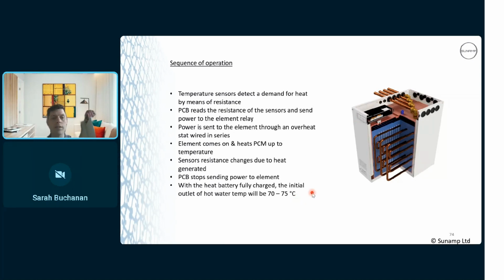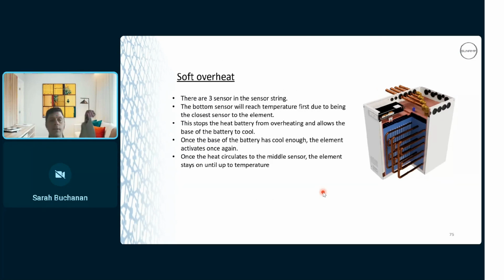With the heat battery fully charged, the initial outlet of the hot water will be 70 to 75 degrees, hence your TMV requirement. Your soft overheat: there are 3 sensors in the sensor string. The bottom sensor reads the temperature first, being closest to the element. This stops the heat battery from overheating and allows the base of the battery to cool. Once the battery has cooled enough, the element activates once again. Once the heat starts to circulate, the bottom sensor, TS1, temperature sensor 1, doesn't exceed its maximum temperature. All right.